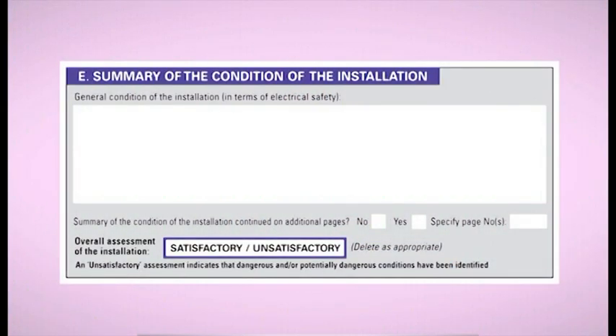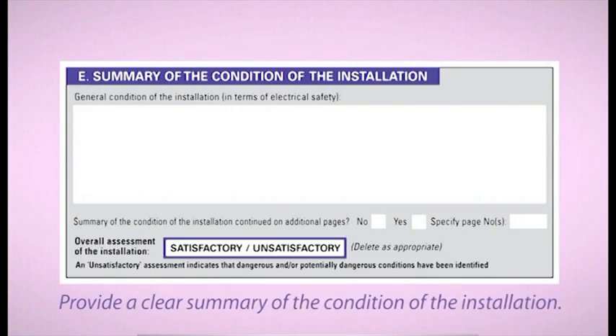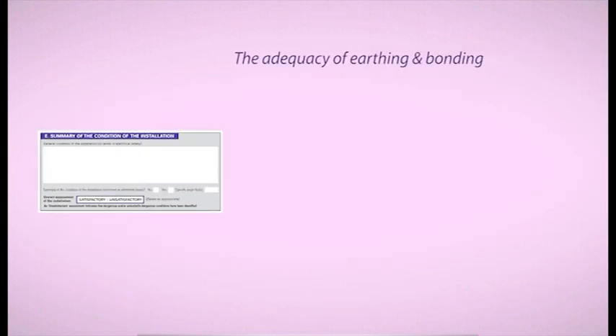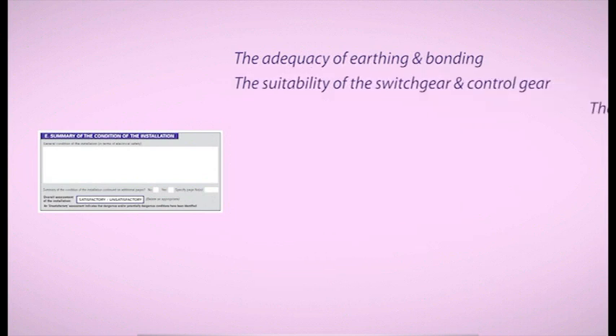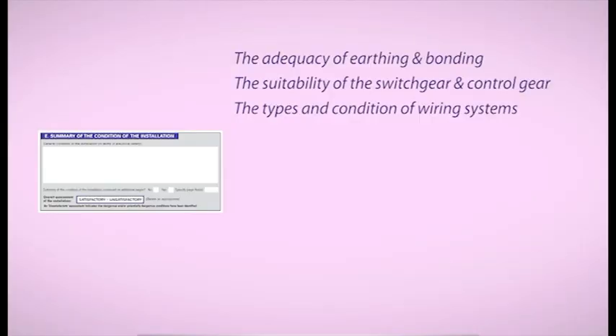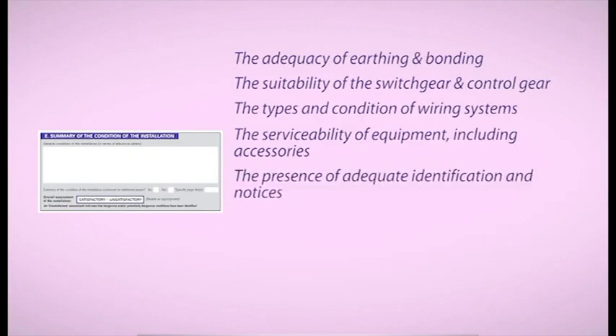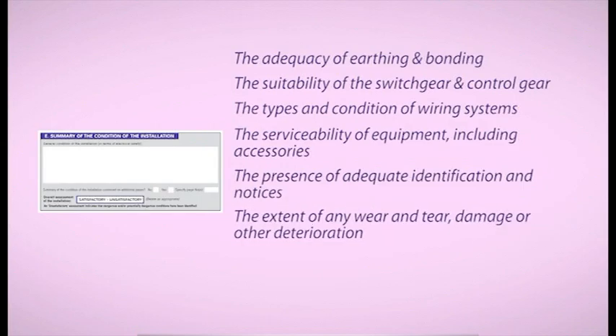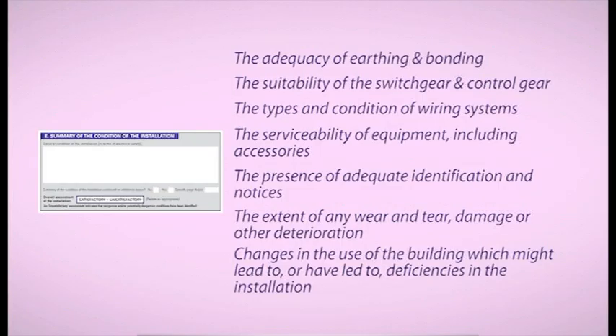The final box for us to discuss on the EICR is the summary of the condition of the installation. Now, I've seen "poor" or "needs a rewire" here, but these are not accurate statements. In real terms, you should provide a clear summary of the condition of the installation, having considered, for example, the adequacy of the earthing and bonding, the suitability of the switchgear and control gear, the types of wiring system and its condition, the serviceability of equipment, including accessories, the presence of adequate identification and notices, the extent of any wear and tear, damage or other deterioration, and changes in the use of the building which have led to or might lead to deficiencies in the installation.